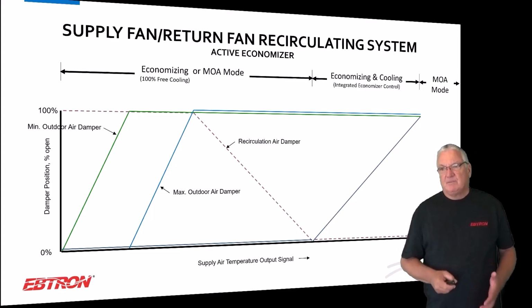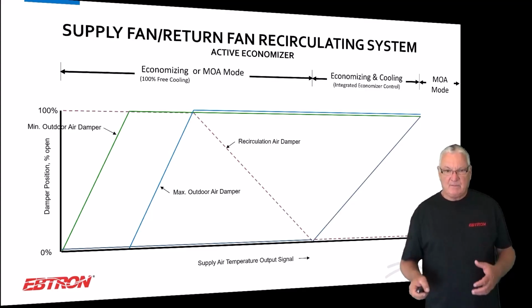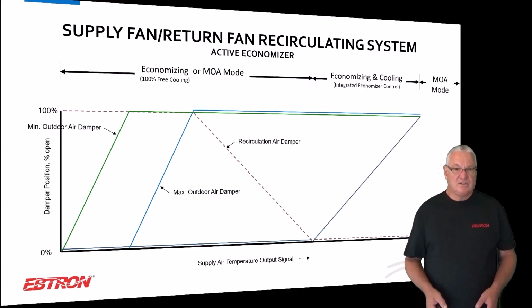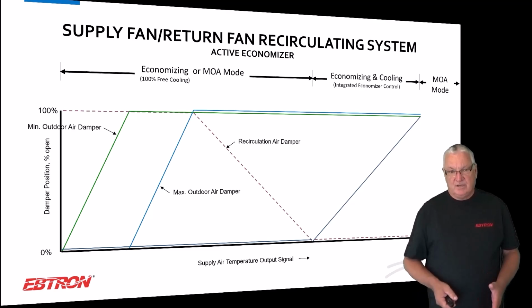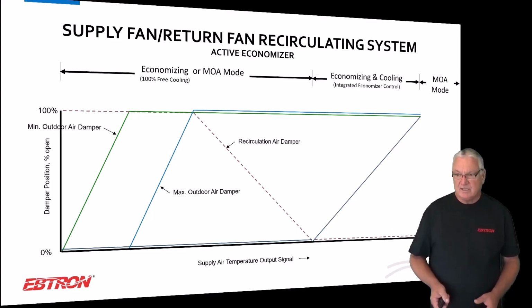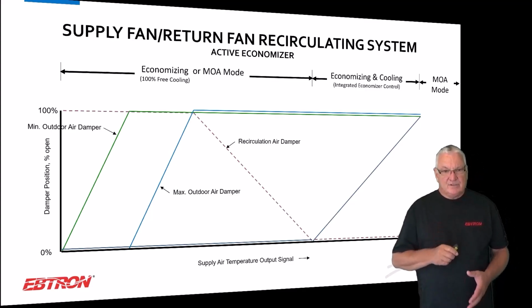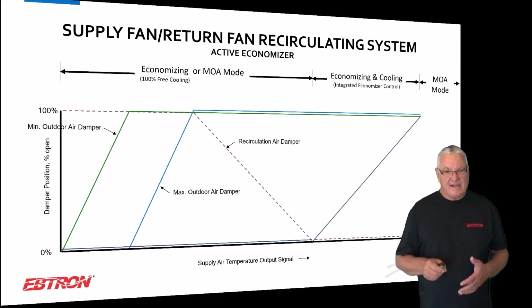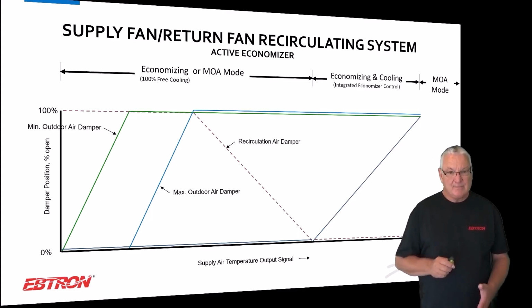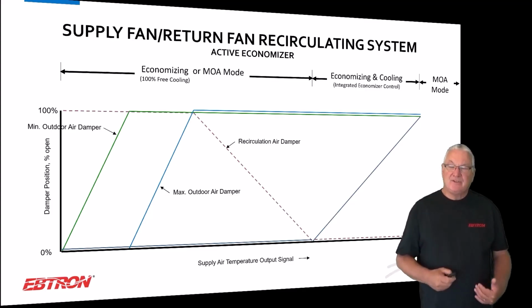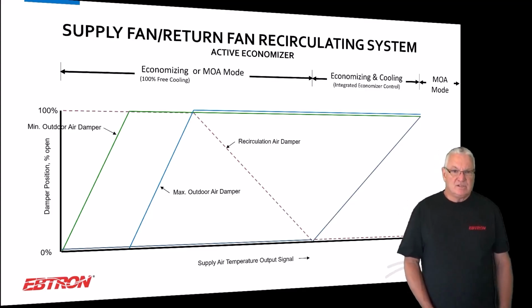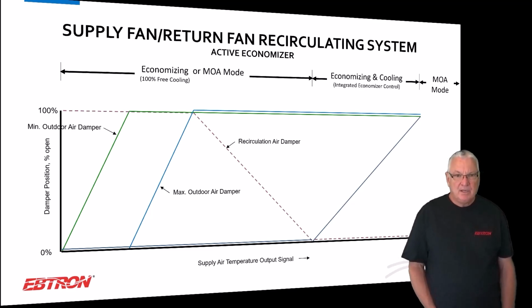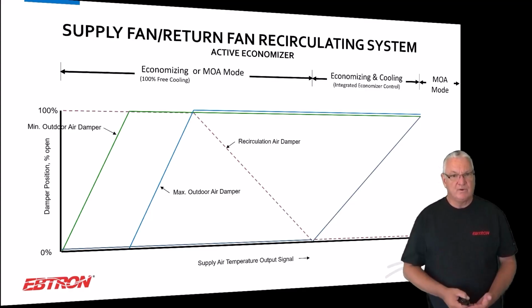When you do min-max, one of the problems with min-max is that the maximum airflow path, when you're measuring it, you could modulate down to a flow that's too low to get reliable measurements. And so you don't really want to do that. In my opinion, you don't want to measure in that path. Also, I've seen, and it doesn't matter whose flow meter it is, when you have these two paths together, there's so much turbulence in that intake plenum that the max flow meter will read something when the damper's closed. So to me, it's not a reliable place to measure. Now, I have plenty of EBTRON customers that are sitting there right now saying, but I do this all the time. That's fine. You've obviously got a way that it's working for you.